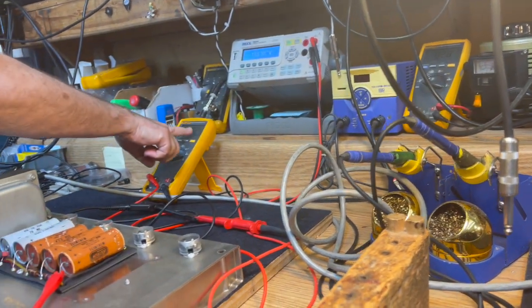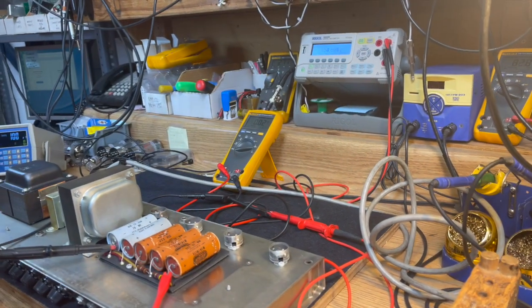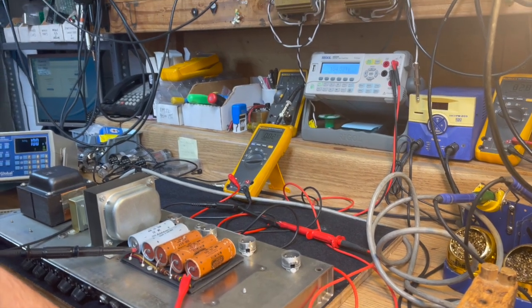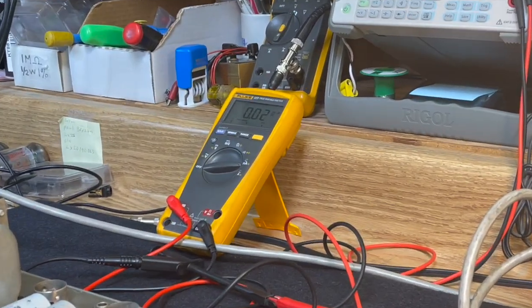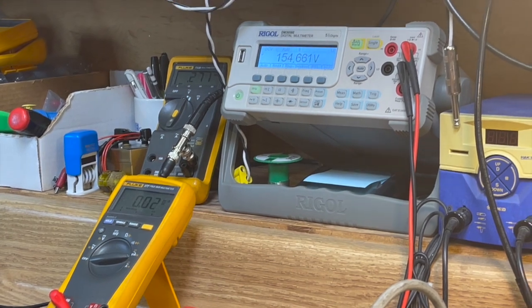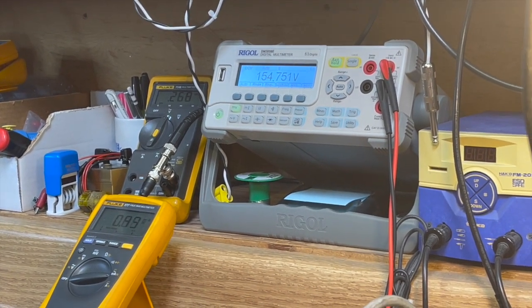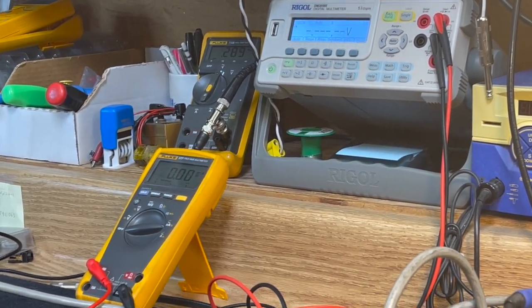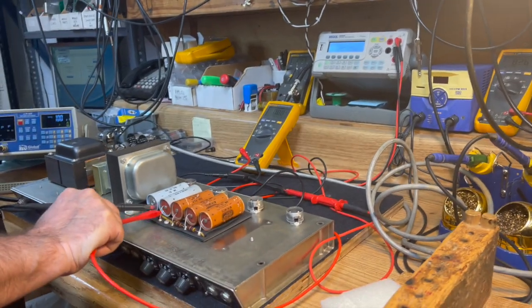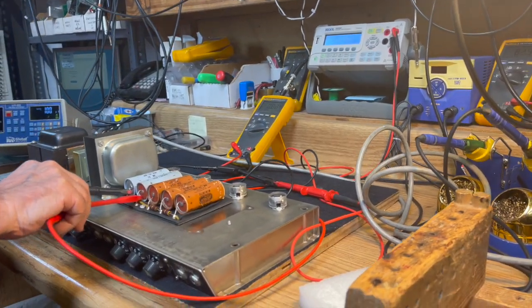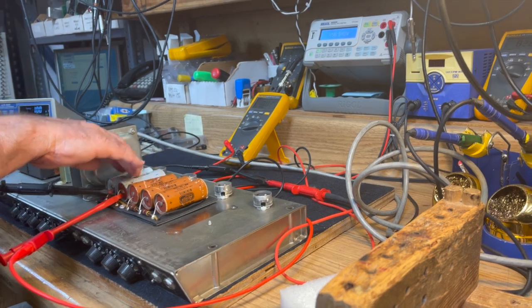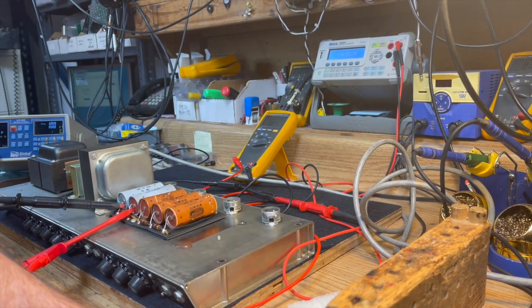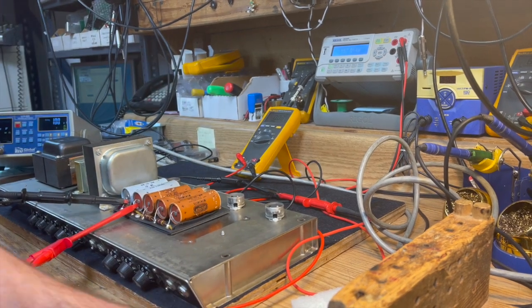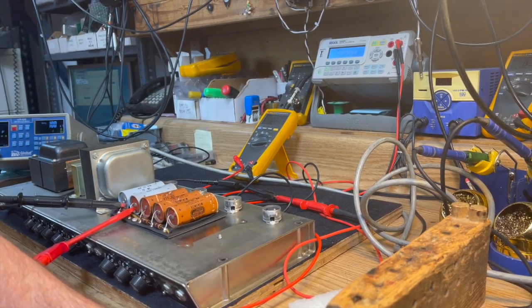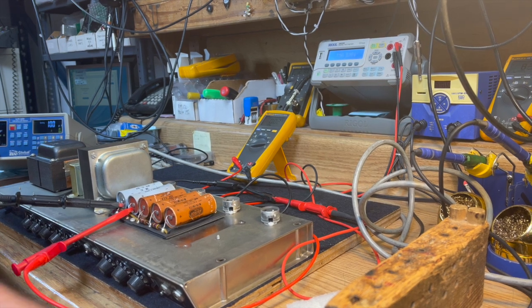And now we see 2 milliamps. So now we're getting up to a significant enough voltage to where we're seeing some leakage and an indication that we might want to proceed a little more cautiously. The main filter caps, the ones that were reading pretty correctly before, are toggling between 1 and 2, so that means it's right at about 1.5 milliamps.